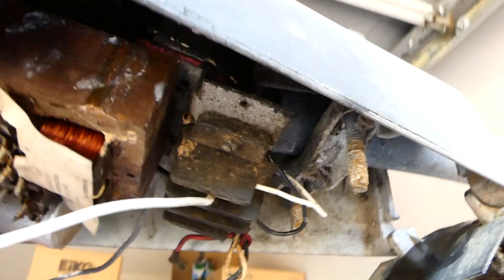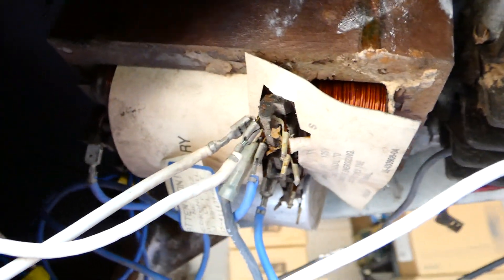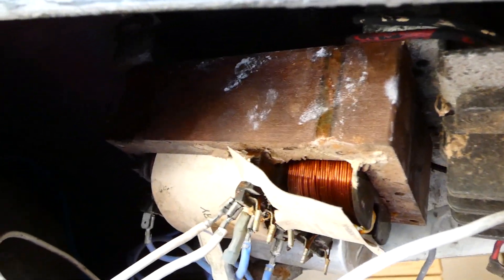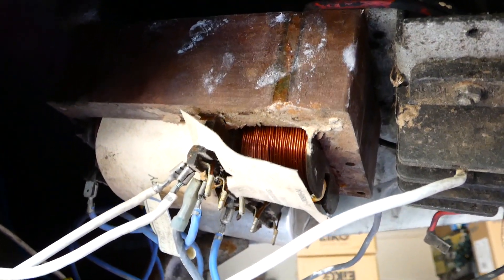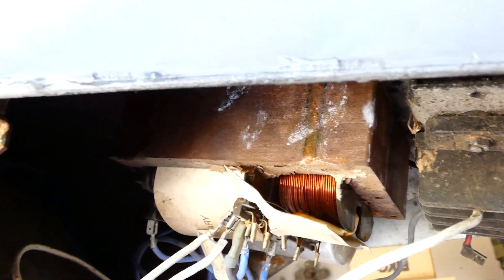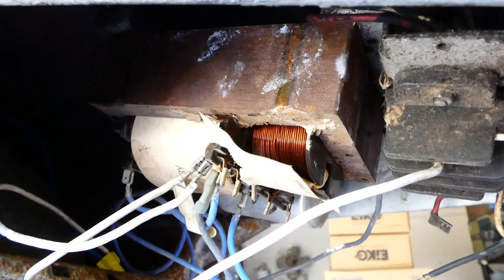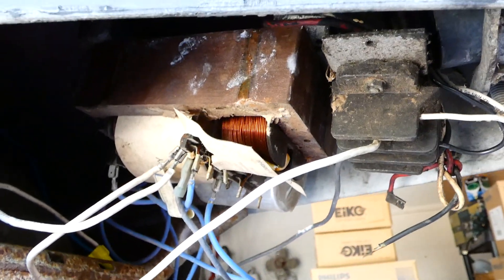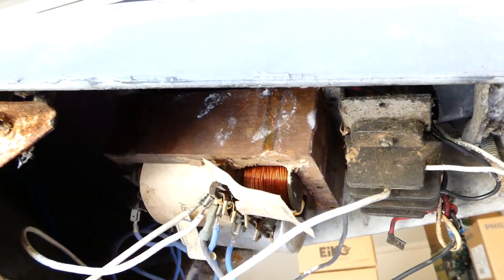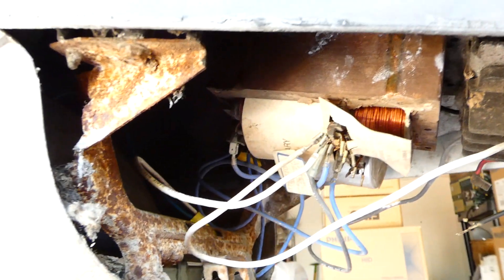Here's the inside of the ballast compartment: there's the Bakelite terminal block — GE standard, doing that even back in the 50s — and a 90s GE M59 H33 ballast. GE has had dual lamp-type ballasts probably since the 70s. All GE ballasts and fixtures in mercury vapor or metal halide literally just came with both a red and a blue tag, and you picked which one you wanted to use so the lineman would know what lamp to grab. These are always metal halide or mercury ballasts, which is cool because usually mercury ballasts can't run metal halide reliably. The photo cell is disconnected, which is why those wires are hanging down.